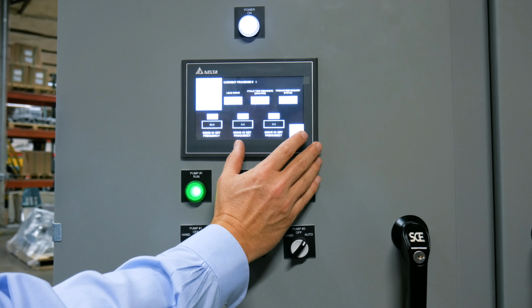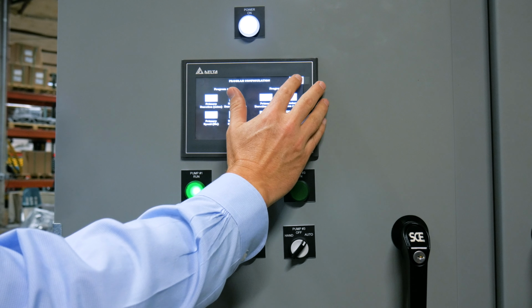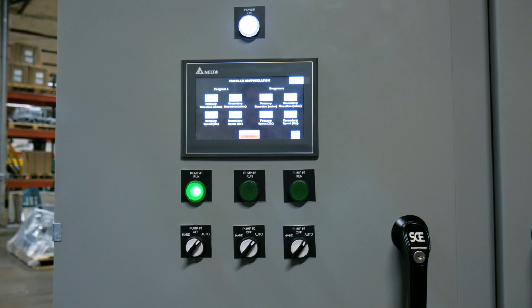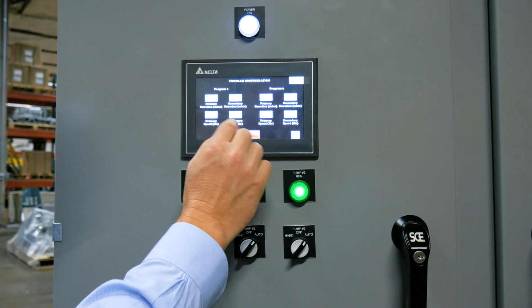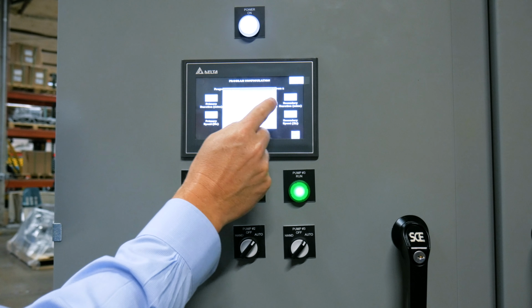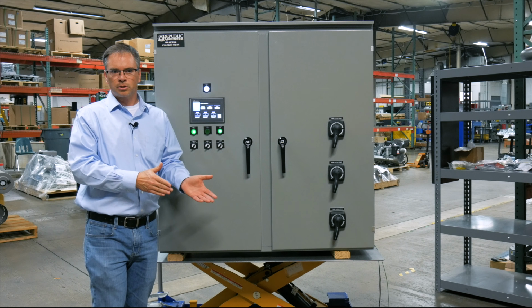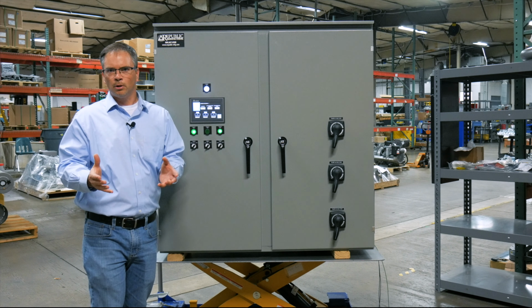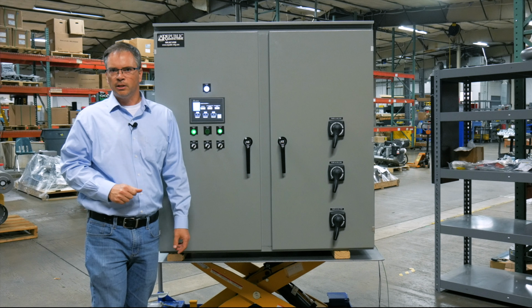This human interface, this HMI, is programmed up. It's got 2 programs in it. Very easy for the user to select. They can run program 1 or program 2. And the different programs will control the speed at which the blowers run, which blowers are on and which blowers are off. And the blowers will cycle through so that each will get a proper amount of run time. So we're going to idle some blowers so that they can rest, and we're going to bring other blowers back online so they can run and keep the aeration pond doing what it needs to.